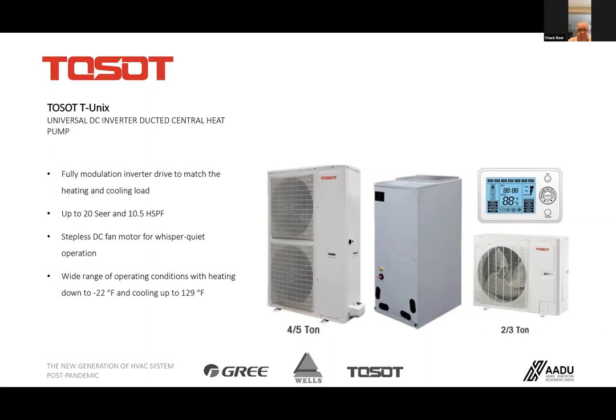We have 2 and 3 ton, and 4 and 5 ton units, going up to 20 SEER. It's 24 volt interfaced, so you're able to use anybody's thermostat or smart technology. The outdoor unit for these systems is designed with ultra heat capacity, and with that in the Northeast we're able to obtain minus 22 degrees at about 80%, and about minus 4 degrees at 100%. So you don't need to use backup heat, which becomes very cost prohibitive. This adds a whole other dimension in the inverter technology world.